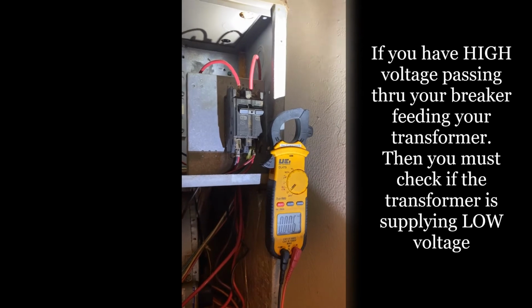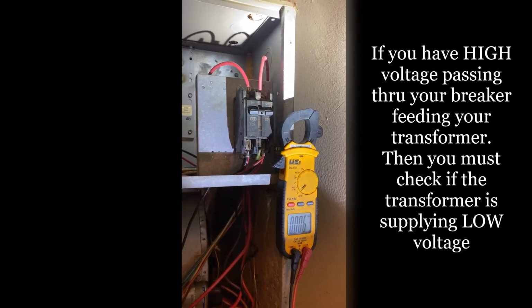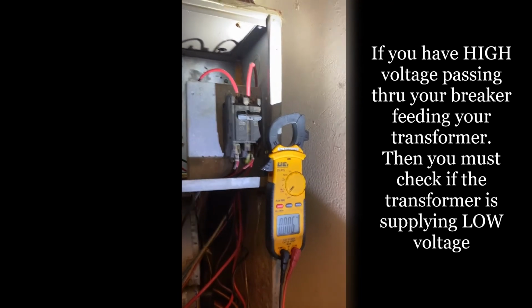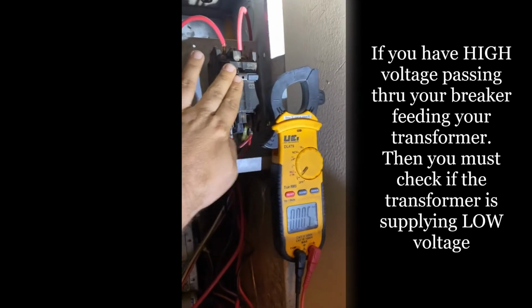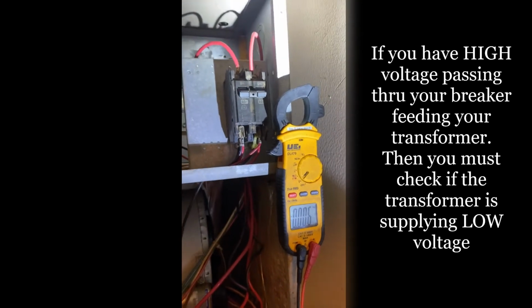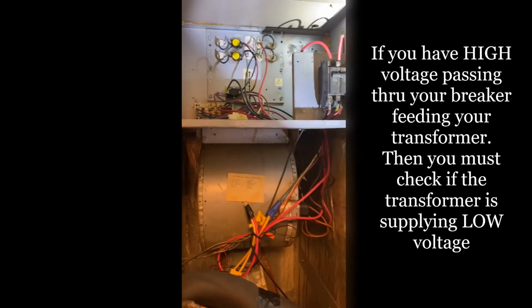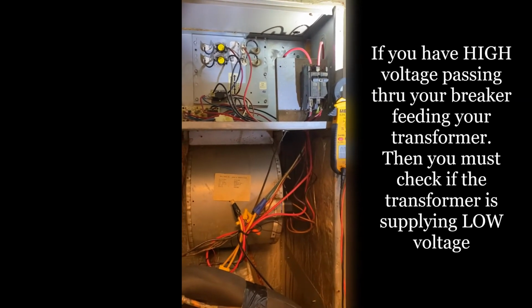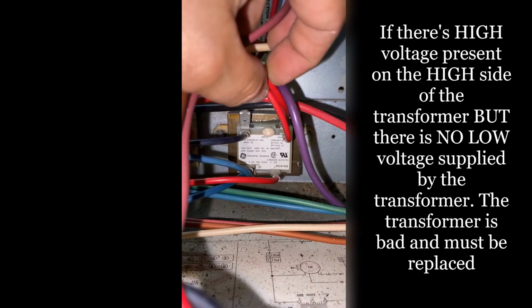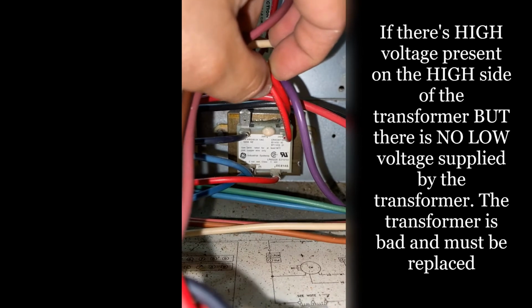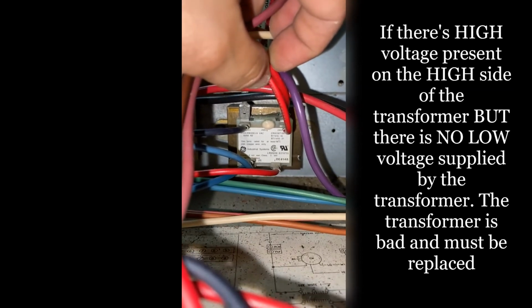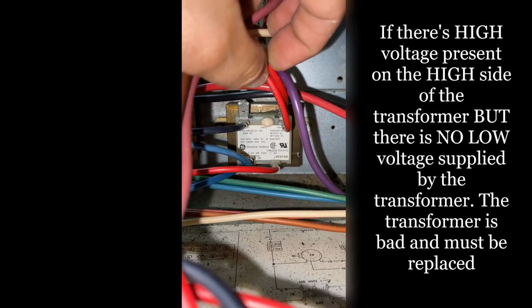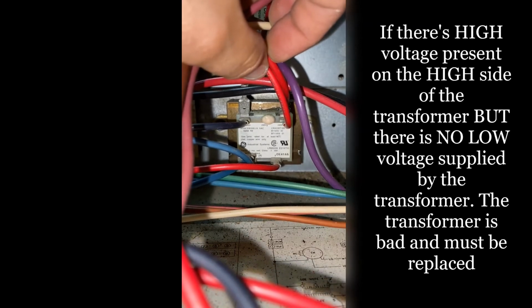So if you do have high voltage coming in, but you still don't have control voltage in your unit, even with this on, then you might have a problem with your transformer. Let's take a look. This is the best shot I can get of this transformer. But basically you'll have your high side and your low side. This is what separates your high voltage and your low voltage.